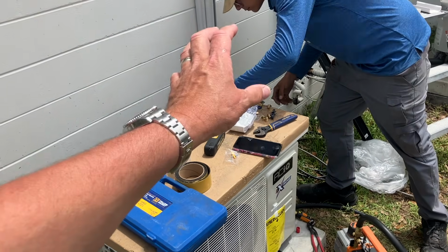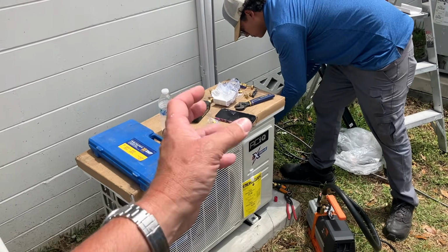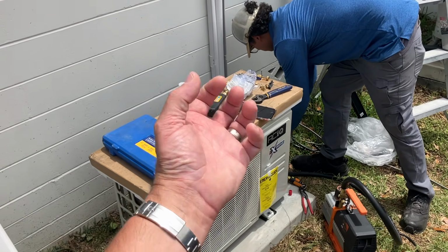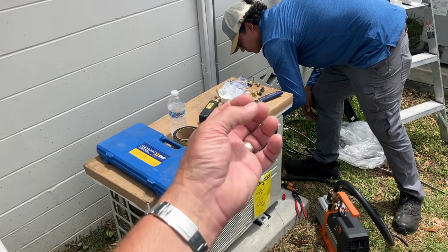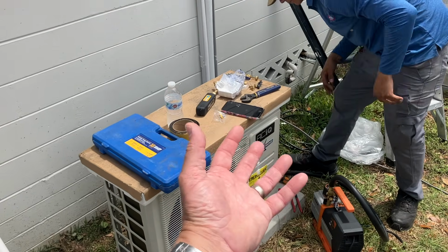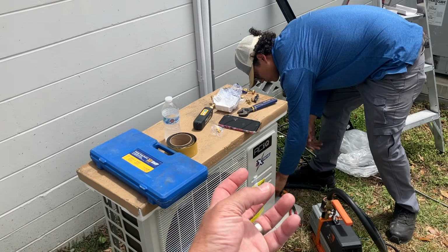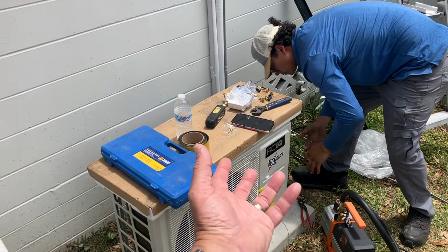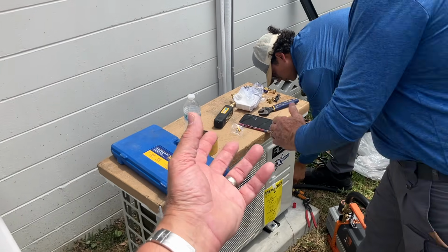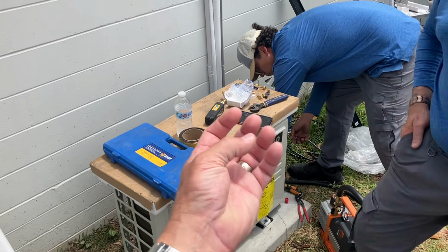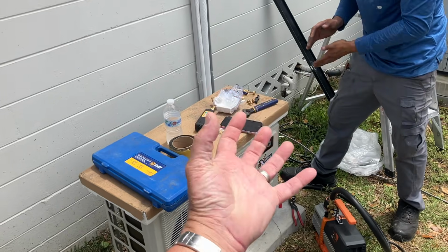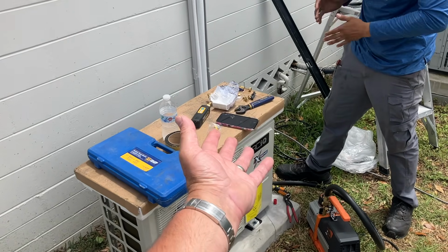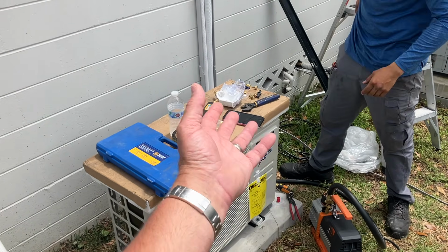It could jump up a little bit or back down, because as we're in that negative atmosphere, in a vacuum, any moisture, which is water, is boiling off, and that's going to expand drastically. That's going to throw off your inches of water column—but you're not in inches of water column, you're in negative pressure, so we measure in microns.